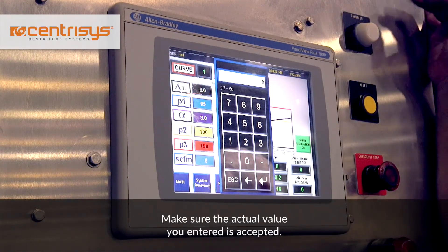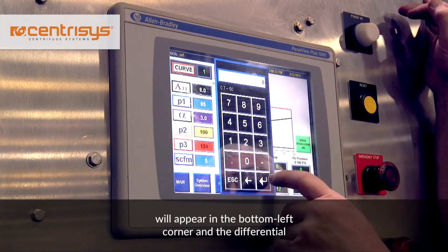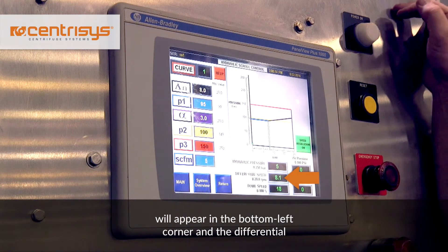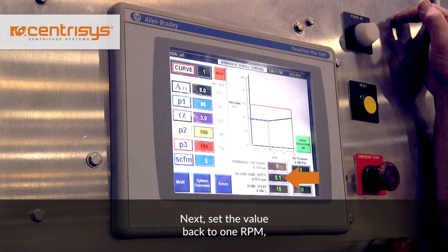Make sure the actual value you entered is accepted. On a Centrisys control panel, this will appear in the bottom left corner in the differential speed box. The actual differential should change to the set value within about 30 seconds.